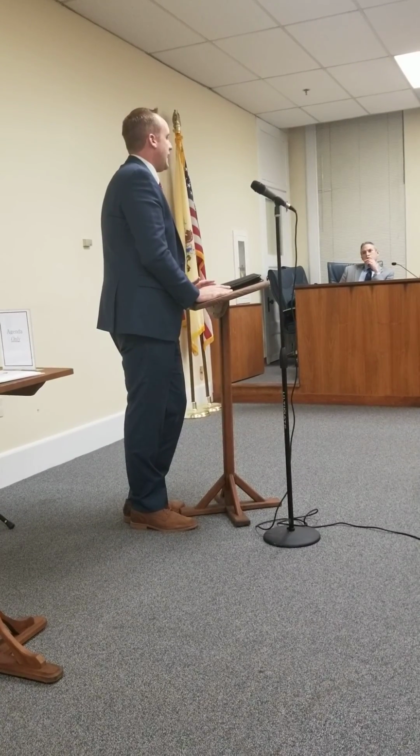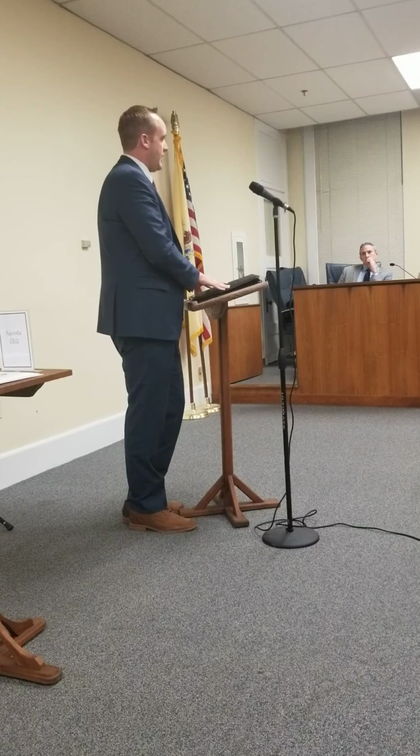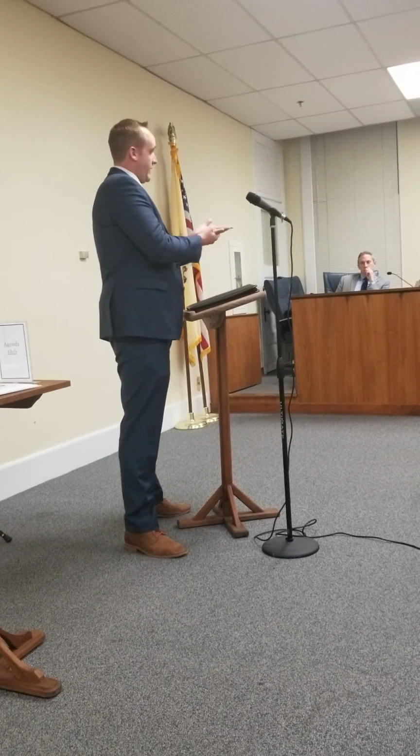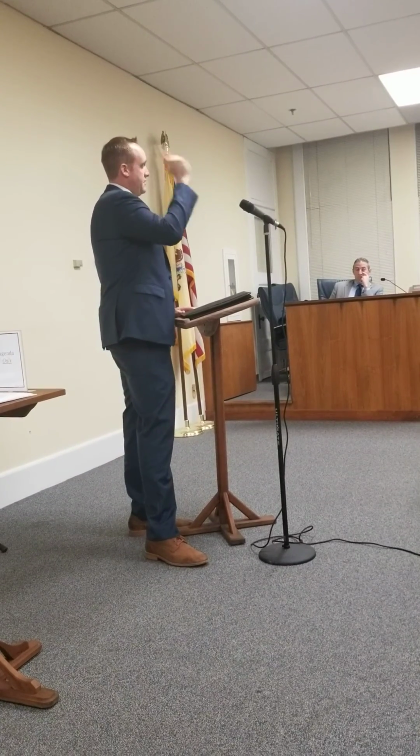This is a device that is mainly instituted right now by Florida Power and Light. But if you're familiar with the electrical service that we provide, you'll see a cutout box where there's a fuse located, and oftentimes when there's an outage, you'll see the fuse in the downward position. What happens from that point is, from a line shop, a troubleshooter or a crew will come out and find the location where the actual fault or where the fuse is blown. Their job after that is to inspect the whole circuit to find where that fault is, as well as if there's multiple faults, to clear them up before they throw those fuses back.